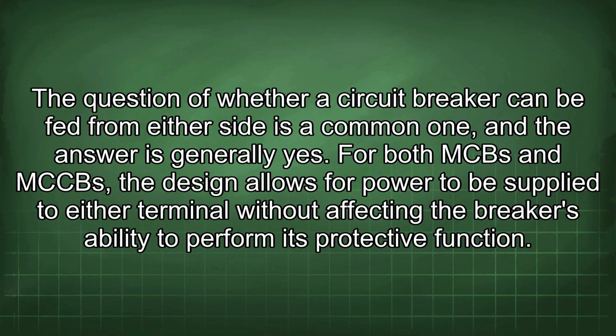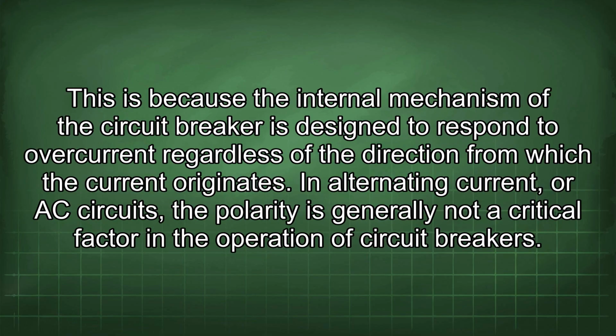The question of whether a circuit breaker can be fed from either side is a common one, and the answer is generally yes. For both MCBs and MCCBs, the design allows for power to be supplied to either terminal without affecting the breaker's ability to perform its protective function. This is because the internal mechanism of the circuit breaker is designed to respond to overcurrent regardless of the direction from which the current originates.